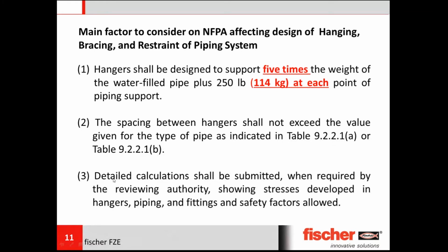Third most important point is detailed calculations shall be submitted when required by the reviewing authority. Now the reviewing authority could be civil defense, it could be an on-site job consultant, to show that the support has been calculated and it is proven to take the weight of the pipe, including all relevant safety factors mentioned in point number 1.